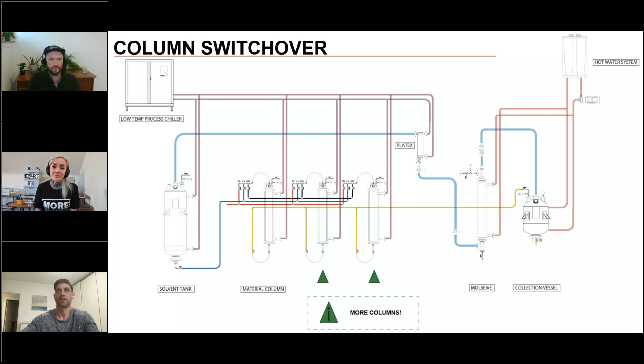That's not true for a lot of systems. If your system requires you to recover the solvent before starting the next set of columns, you really have to measure the entire cycle time and divide it by the number of columns. Getting set up for half the day and running all your columns in a couple hours doesn't count -- you really need to average over the day.